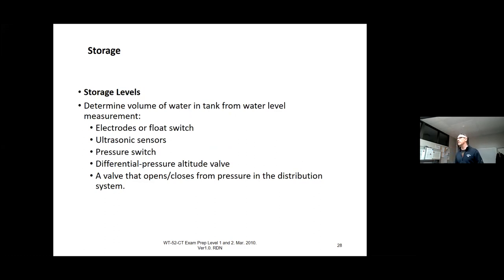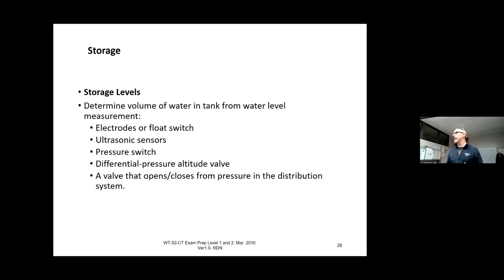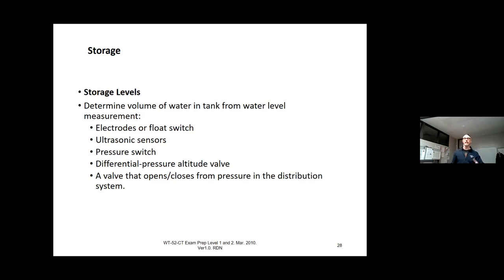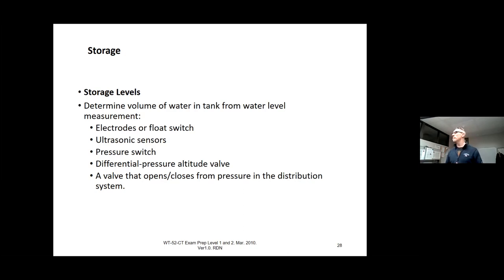Storage levels — your staff will go out and look at your storage levels, usually just a number on the tank on your SCADA, telling you the tank is at 50 or 60 percent. But let's make sure it's actually working. There are a number of different ways you can read level from a tank: you can use an electrode or float switch, an ultrasonic sensor, a pressure switch at the bottom sensing the pressure of the water which corresponds to a level, or differential pressure.